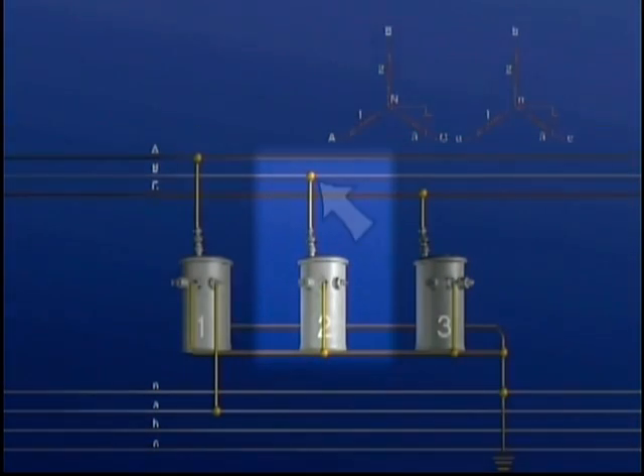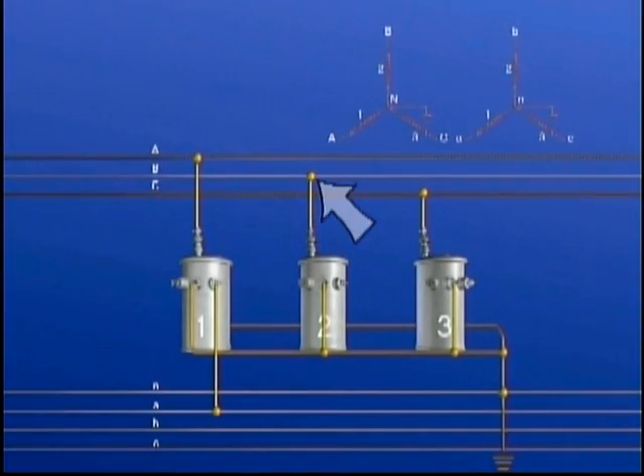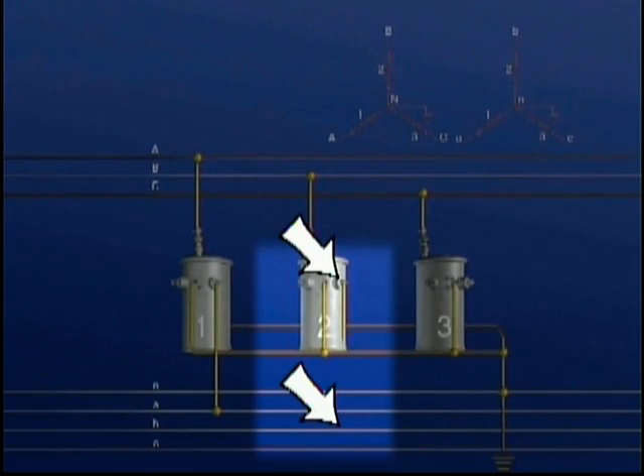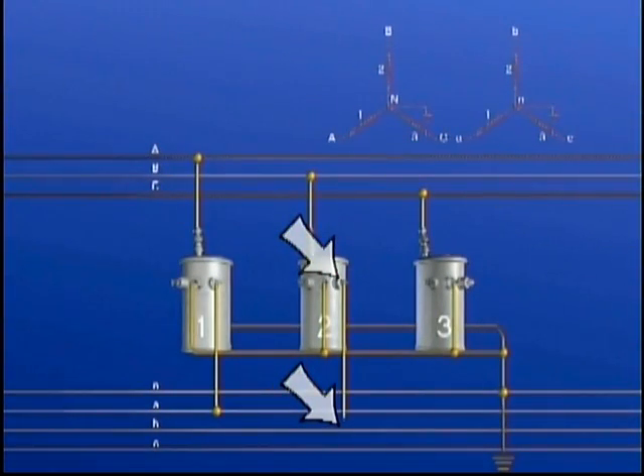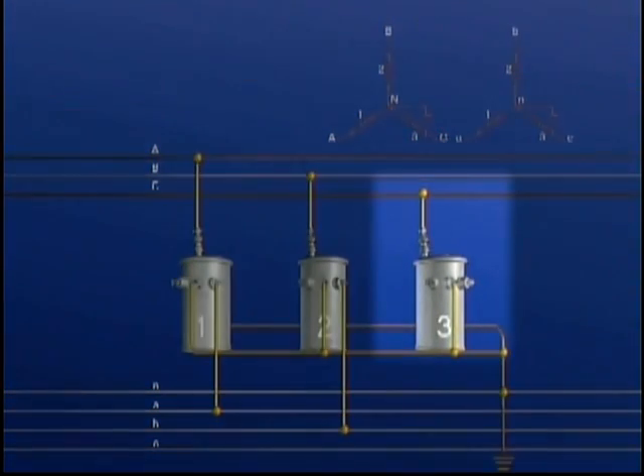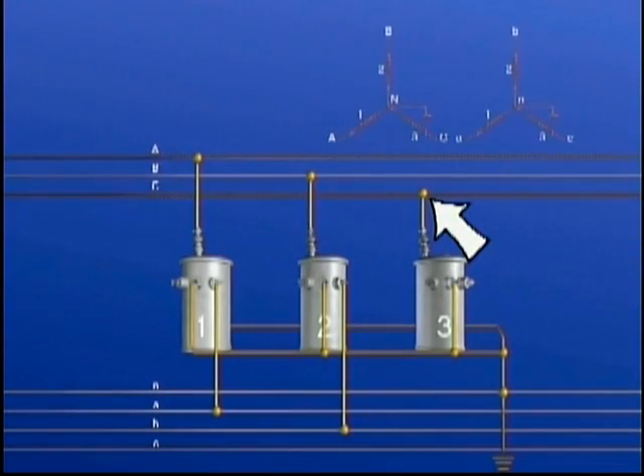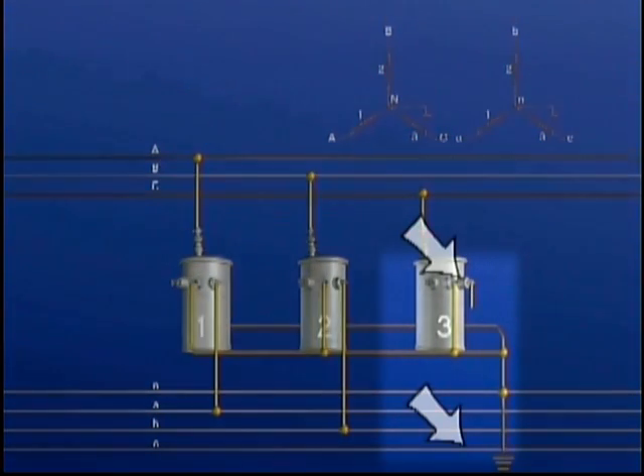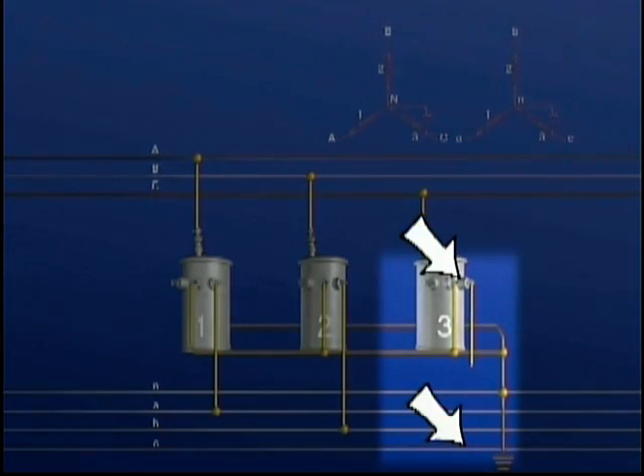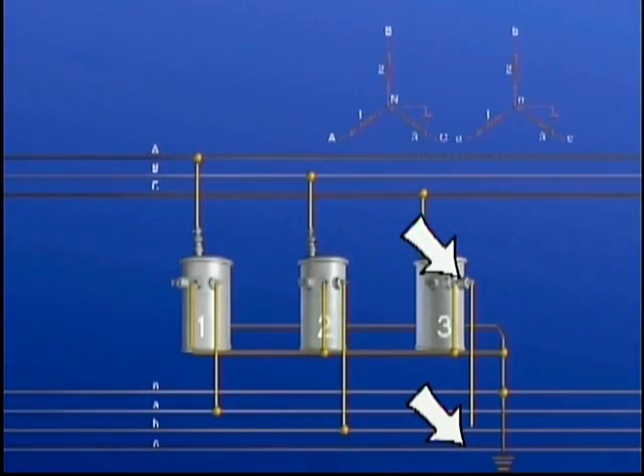Transformer number 2 is connected on the primary side to phase B, so the secondary connection will be made to secondary line B. Finally, transformer 3 is connected to phase C on the primary side, so the secondary X1 bushing is connected to secondary line C. When this is done, there is no phase shift between the primary and the secondary windings of the 3-phase bank, so it has 0 degrees angular displacement.